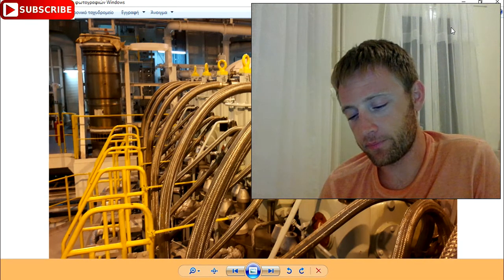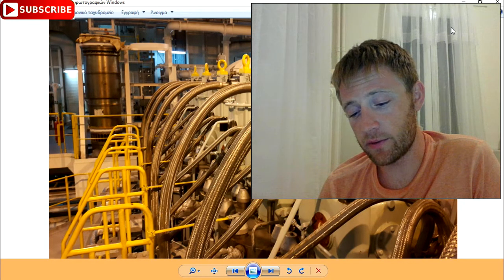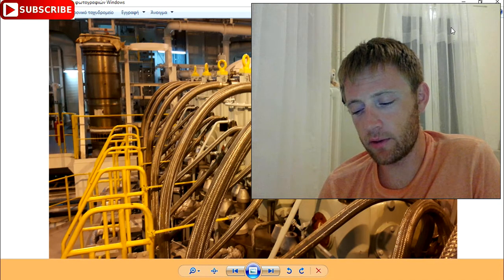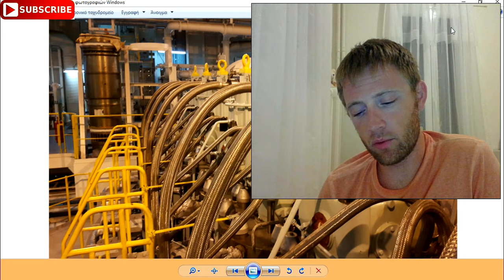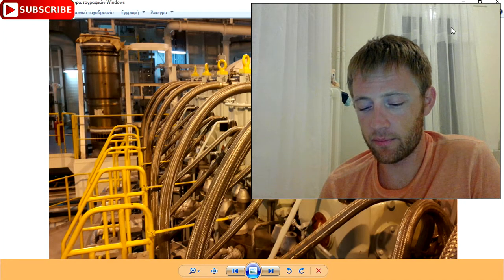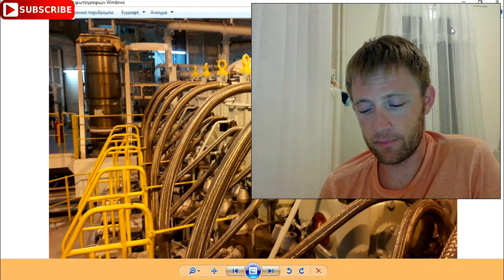Okay, 30. If a system pressure control valve is not working, we close the isolating valve and we put the manometer. We open the manual pressure control valve, and the manometer must show 60 to 65 bar. To increase pressure, okay, I close with an Allen key to increase pressure. This is the procedure, okay.